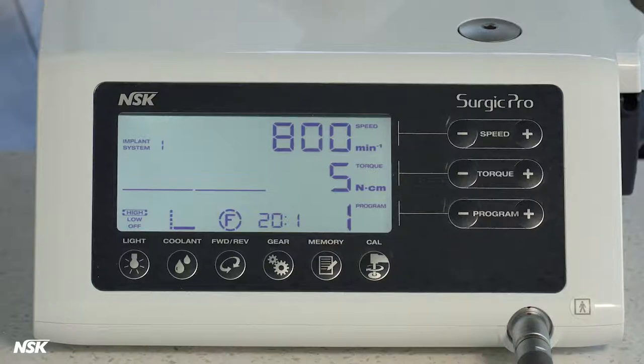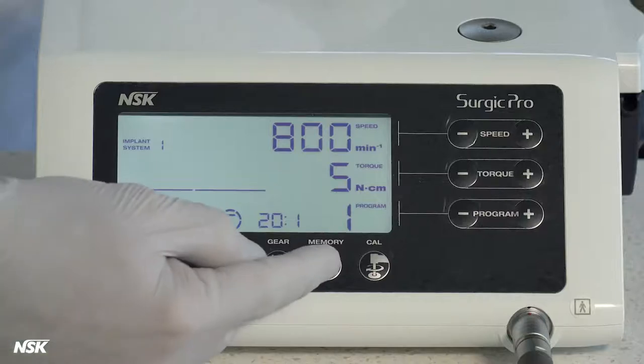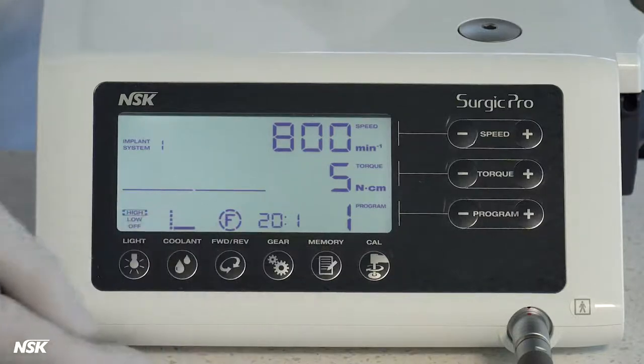Memory button is used to store the parameters of a custom setting in a program. After choosing the proper speed, torque, gear ratio, forward or reverse, and coolant flow, simply press the memory button for two seconds until you hear a beep to store the settings. You can store up to eight programs for eight different implant systems.